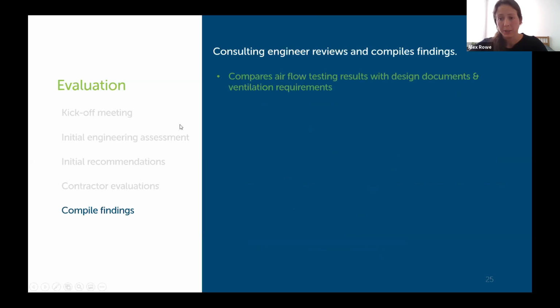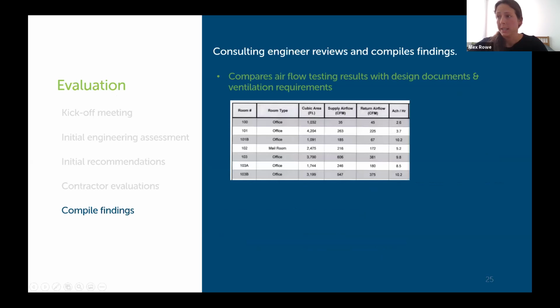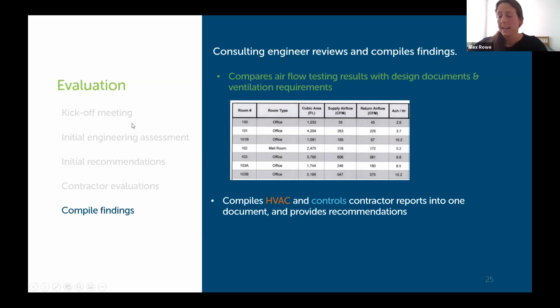Then back to the consulting engineer, who reviewed all of the evaluation results and compiled those findings. So they then compared the airflow testing results with design documents and ventilation requirements in order to see if the HVAC system is operating as designed and per ASHRAE 62.1 ventilation requirements. And the engineer also compiled all of the HVAC and control contractor reporting and documentation into one document and then provided recommendations for improvement.